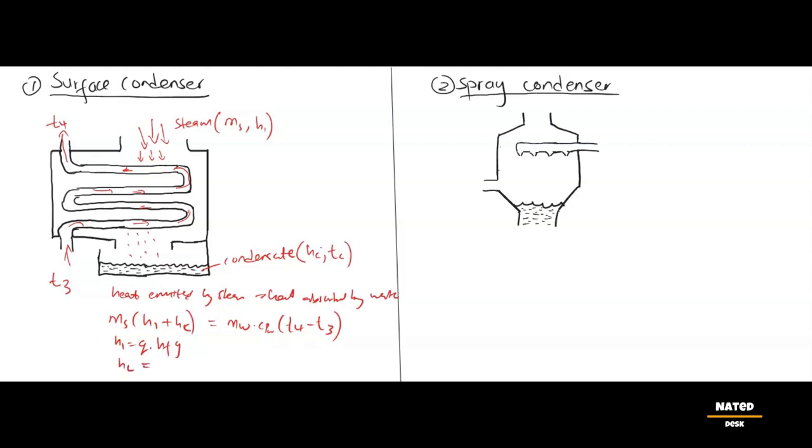hc is heat enthalpy of the condensate, which equals cpw(ts - tc), where cpw is specific heat capacity of water at 4.187 kJ per kg kelvin. cpw is always this value, never changes.